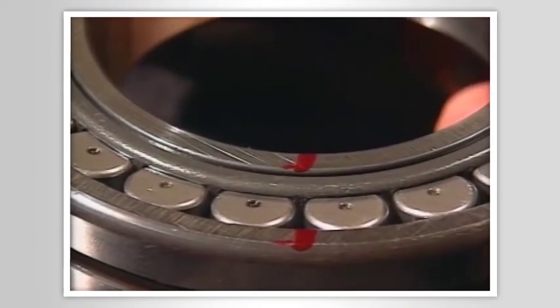When we look at the manufacturer's ball pass frequency inner race, we find a value of 12.04, and we now know what the value means. It's the number of rolling elements that a specific point on the inner race will pass with each rotation of the shaft. If the mark on the race represents a rough spot, a ball pass frequency inner race vibration will be generated at 12.04 times the turning speed of the shaft. The resulting frequency we would refer to as a fault frequency. The number provided by the manufacturer is often referred to as a multiplier of shaft speed.